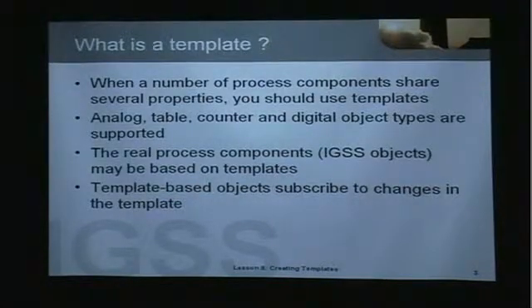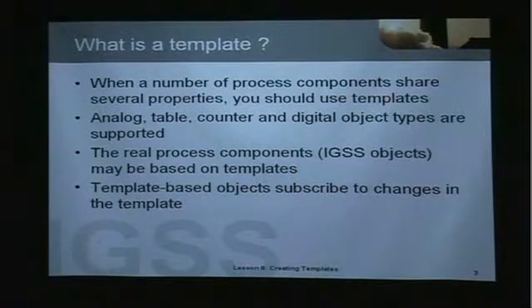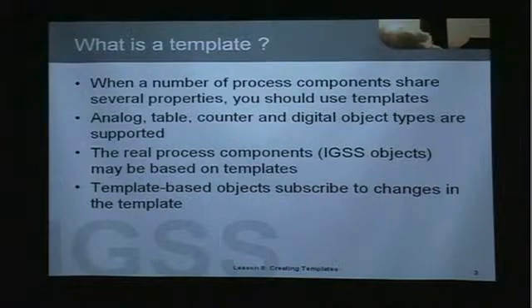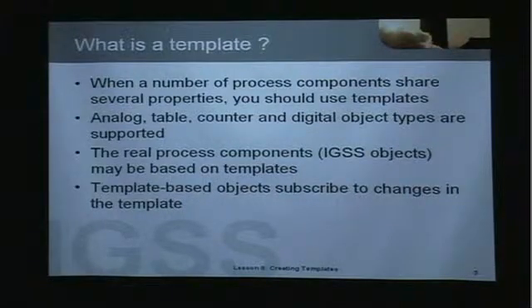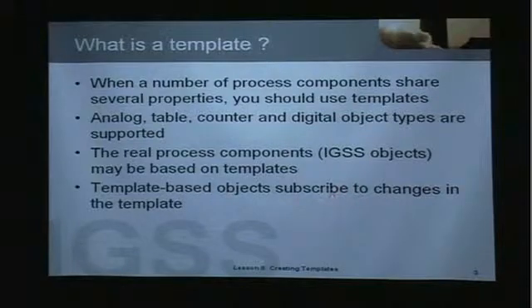When you have a number of process components that share several properties, you should use a template in IGSS. You can create templates for analog, table, counter, and digital objects. The real process components or IGSS objects may be based on a template, and this is our recommendation because you will save a lot of time. The objects that you base on a template will subscribe to any change you go back and make in the template.